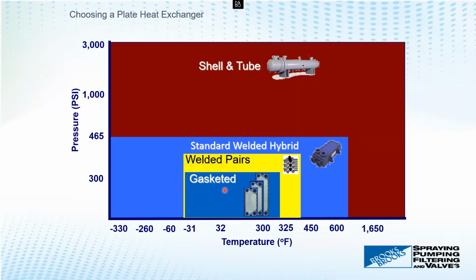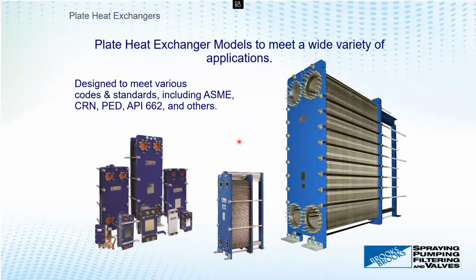So let's dive in and talk about some gasketed heat exchangers. First thing you want to talk about is, can I use them in my system? People are worried that you have to use ASME. Obviously in Canada, we need CRN, and fear not, all APV heat exchangers, and all plate and frame heat exchangers by other manufacturers, as far as I know, are CRN registered all across Canada, ASME made. So all those codes and standards are up to speed, and they're used everywhere in the world. There's not a country or an area that is not using plate and frame heat exchangers. So should you have to send projects into the Middle East or into Africa or Asia, by all means, you're going to be able to meet the codes and standards of the local area and classifications. So take all that worry out of your mind. It's more about the process, not the codes and the standards. So we'll be able to get that.